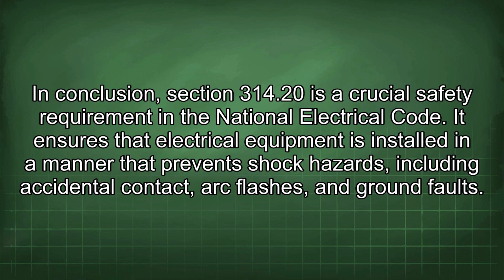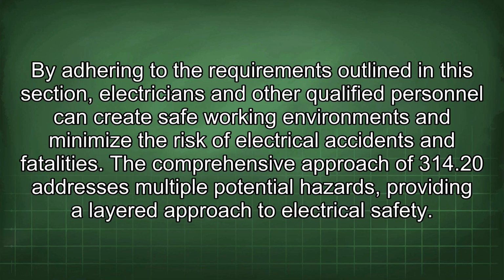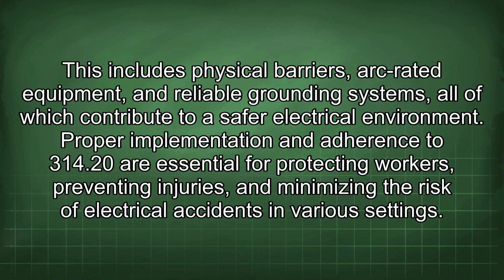In conclusion, Section 314.20 is a crucial safety requirement in the National Electrical Code. It ensures that electrical equipment is installed in a manner that prevents shock hazards, including accidental contact, arc flashes, and ground faults. By adhering to the requirements outlined in this section, electricians and other qualified personnel can create safe working environments and minimize the risk of electrical accidents and fatalities. The comprehensive approach of 314.20 addresses multiple potential hazards, providing a layered approach to electrical safety. This includes physical barriers, arc-rated equipment, and reliable grounding systems, all of which contribute to a safer electrical environment.